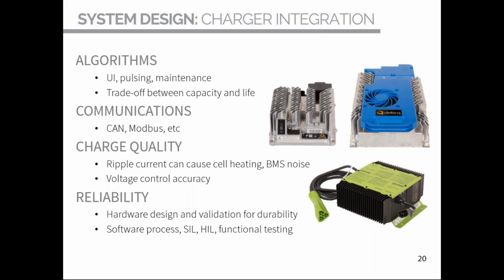Now, voltage control, accuracy, and control stability are also very important. They're critical for performance, life, and safety of lithium-ion. We were talking about how you've got to have a trade-off between how much energy you decide to cram into the cells versus how much life you're going to get out of them. And this is where it's particularly important to control the voltage. This is actually very true for the LFP chemistry that's used by Discover, as we found in our testing.